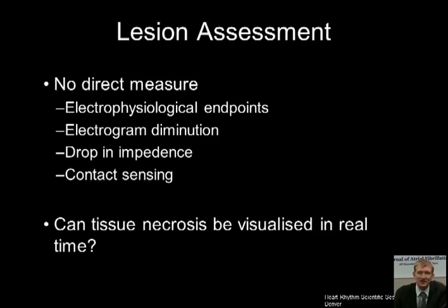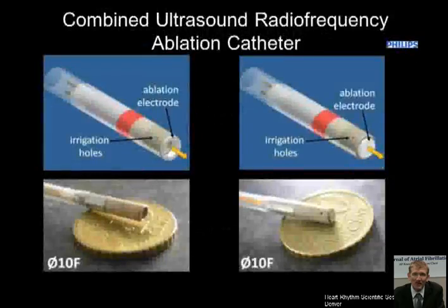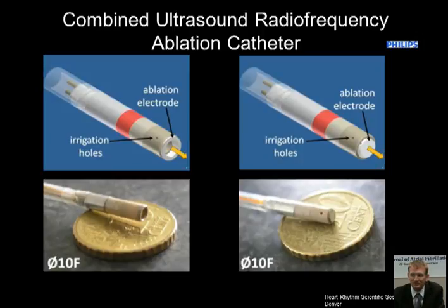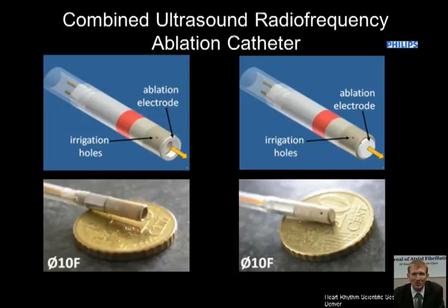So what we set out to look at is whether tissue necrosis can be visualised in real time during the ablation. To do this, we developed a combined radiofrequency ultrasound catheter, and with this catheter we are able to both ablate and see lesion formation with a single catheter. We developed a number of prototypes. One is an open-ended ring catheter design, where the ultrasound does not have to pass through anything other than the irrigation fluid to get to the tissue. Another, called the TPX catheter, has a fine membrane over the end which can hold current but also allows ultrasound waves to pass backwards and forwards so we can see changes in ultrasound contrast.